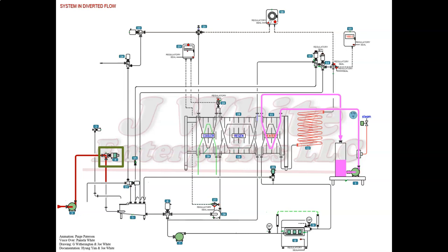The balance tank inlet throttling valve holds the balance tank at a constant level. The balance tank maintains a near constant level so the booster pump or stuffing pump will have a consistent inlet suction pressure at all times.